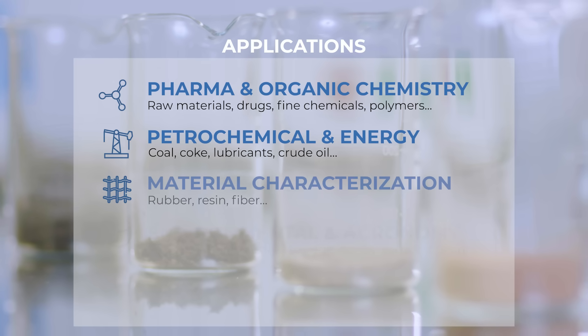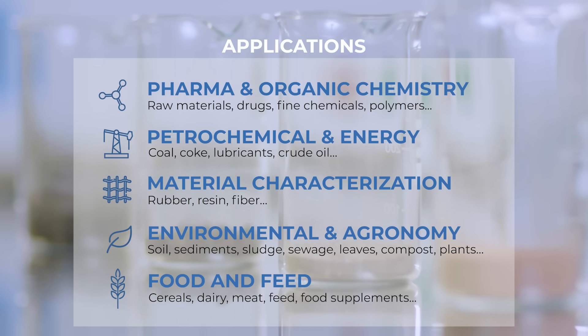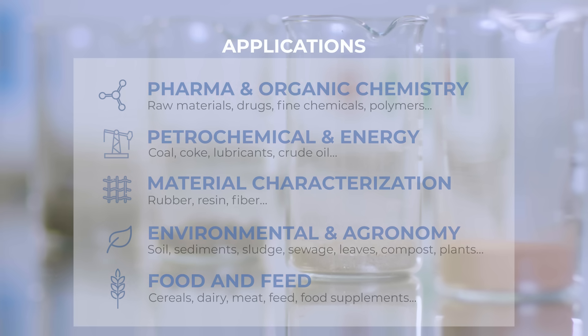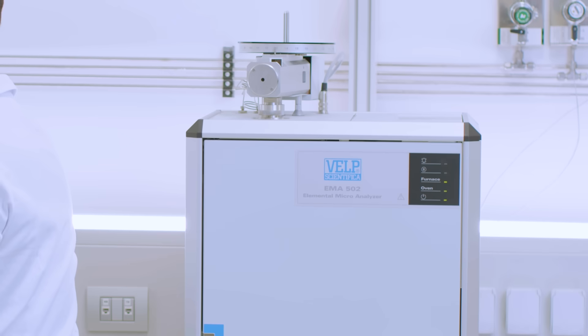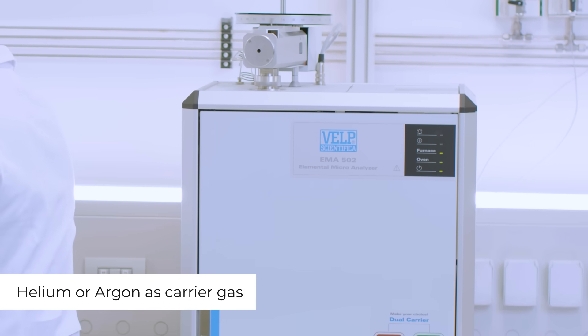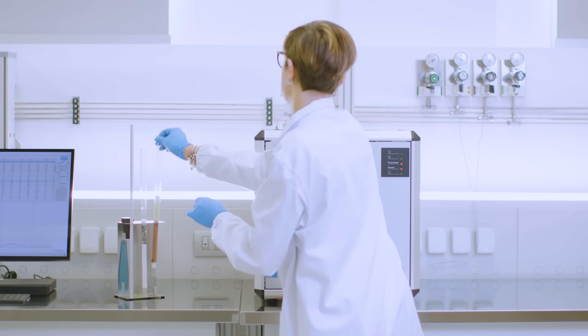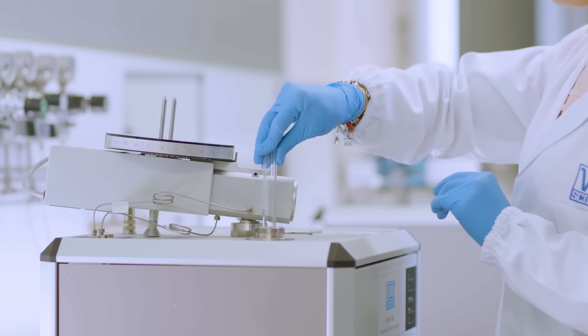EMA502 provides scientists with a safe and reliable solution for the quantitative determination of multiple elements simultaneously, and is used to evaluate the structure, purity, and chemical composition of a sample. The EMA502 works with helium or argon as a carrier gas without the need for any hardware modification and is designed for easy routine maintenance.